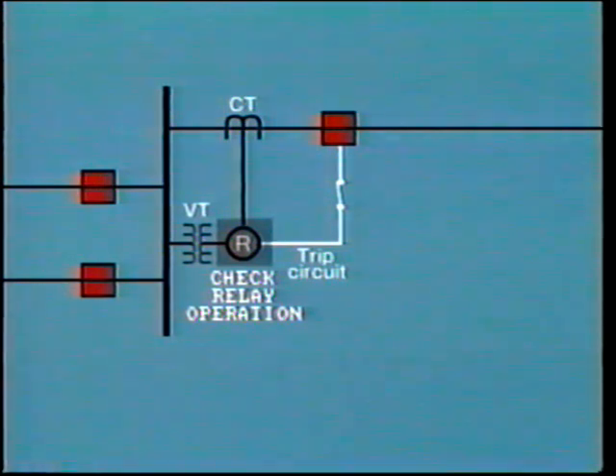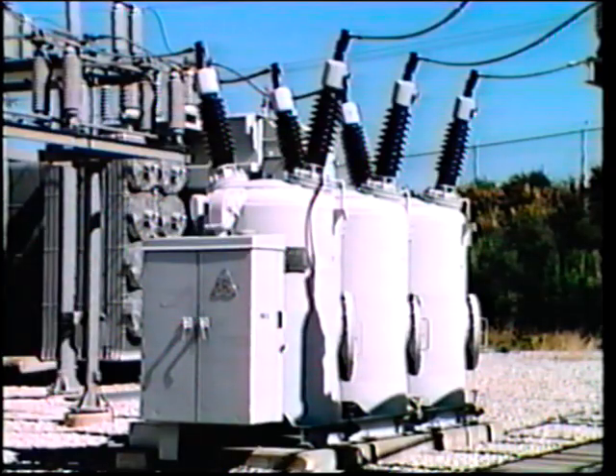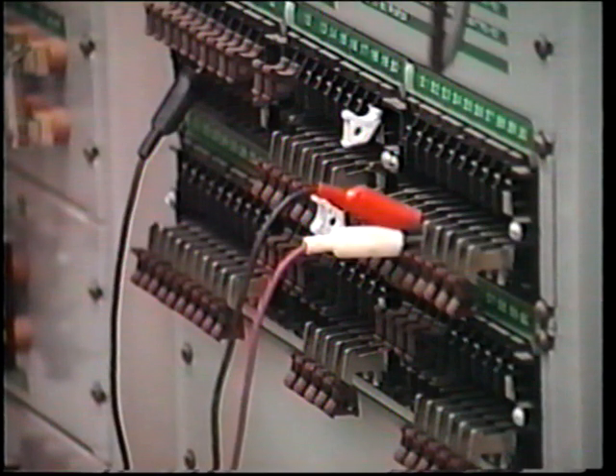Because the line is still in service, it is essential to disconnect the relay output so that actual tripping will not take place. Remember, we cannot disable the tripping circuit at the breaker because this is still in service and must be able to trip from other sources. The relay output may be isolated by switches, sliding links, or test plugs which are provided for this purpose. In some cases, there may be no alternative but to disconnect wires.